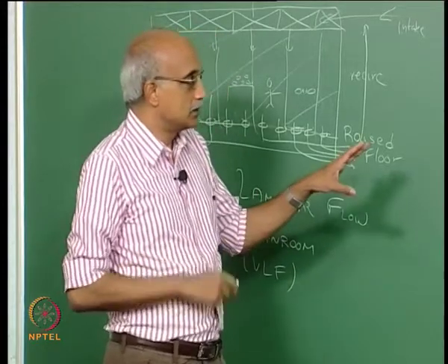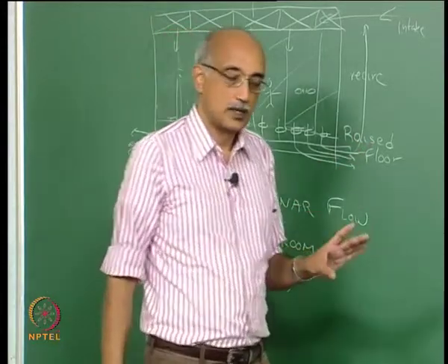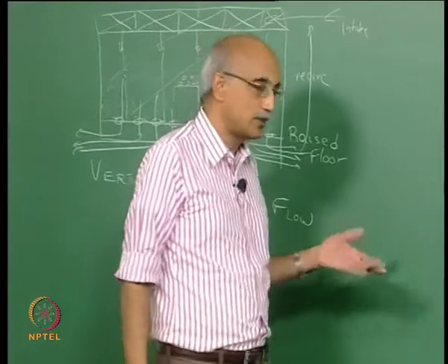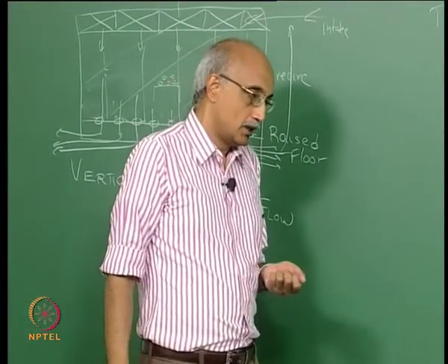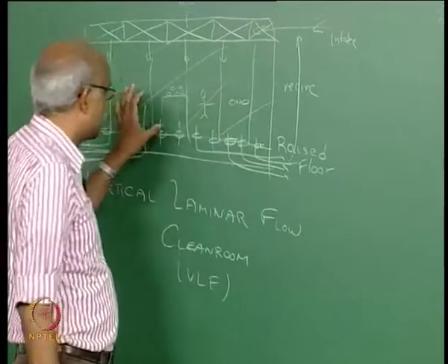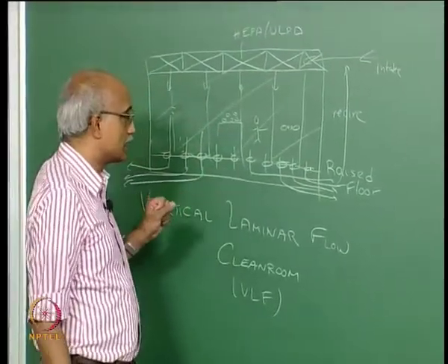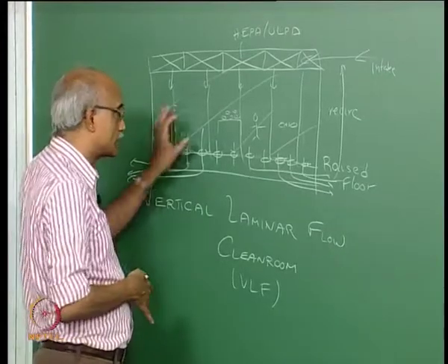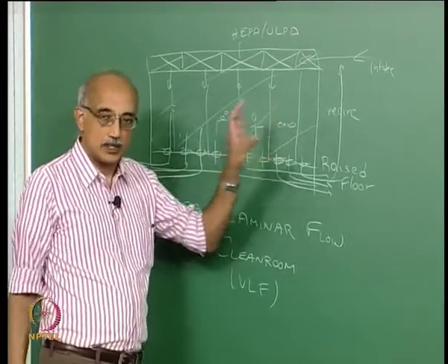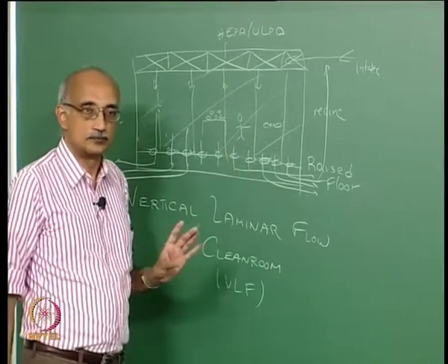So, instead what you can choose to do is develop a simpler model for a clean room. For example, you can assume that the clean room is essentially well mixed, so that particle concentrations everywhere inside the clean room are uniform.